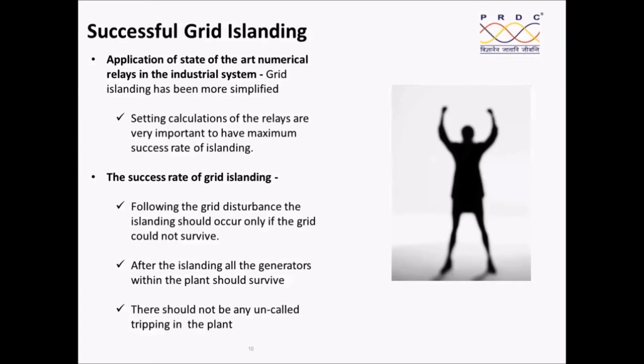If the grid survives and I still get islanded, then the sensitivity of my islanding is very, very high. What it implies is that I am unnecessarily losing the grid. After the islanding, all the generators within the plant should survive. We have to ensure that within the plant the maximum generation is surviving and also the maximum production is surviving. There should not be any uncalled tripping in the plant. Yes, if there is an excess load, I can trip the load, but there should not be any uncalled tripping in the plant. This is very, very important in the case of grid islanding.